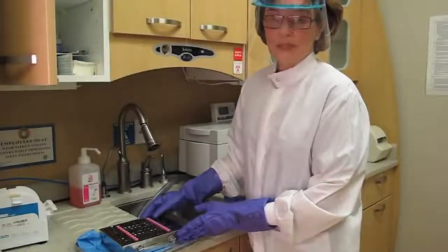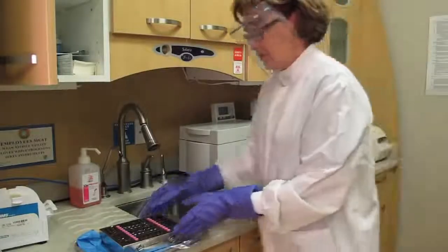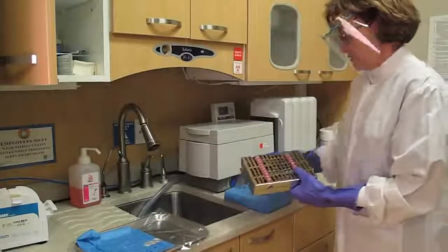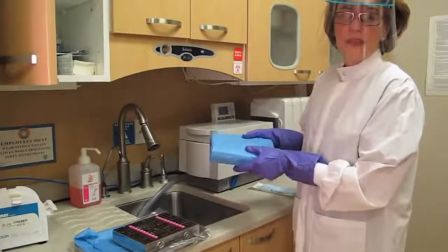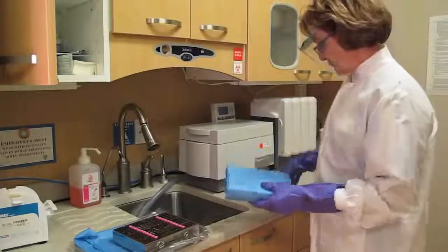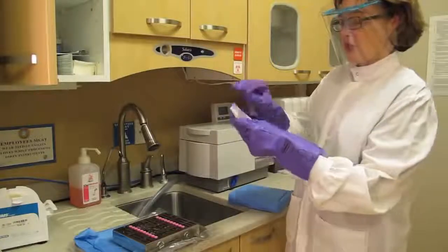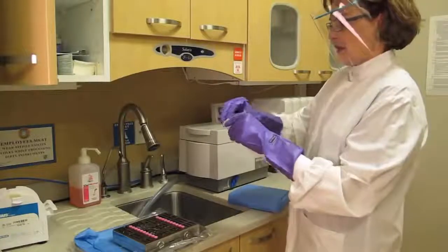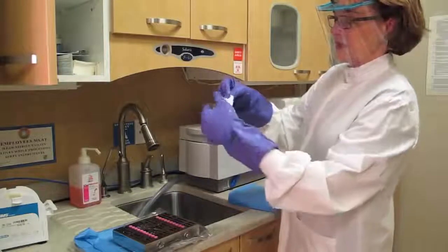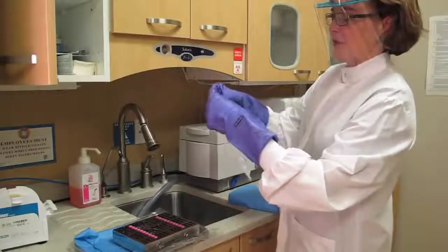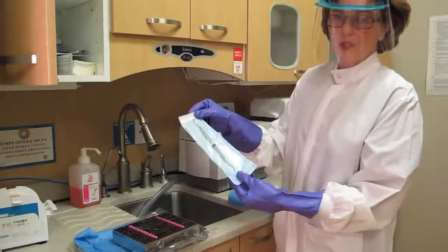After your instruments are pre-cleaned and they're on the dirty side of the sterilization room, you want to pouch them or wrap them in wrap. So they're ready to go. They need to be dried and wrapped, and then they go into the sterilizer. If you have individual instruments or you're using pouches and you're not using cassettes, make sure that the pouches are new each time, never reused, and that they're folded so that the seal actually does prevent air from getting into the package, and that way it can remain sterile until it's used.